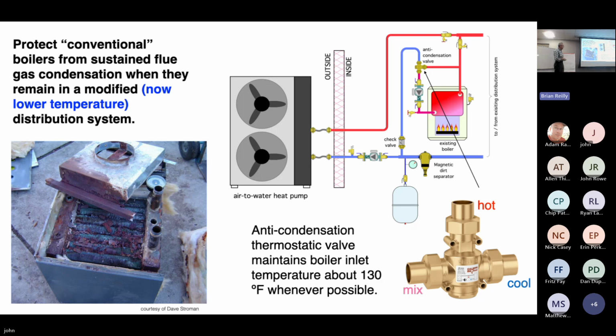Again, this is what happens when you run a conventional boiler at conditions that allow sustained flue gas condensation. That's an example of one of those thermostatic anti-condensation valves. Caleffi makes them, Danfoss makes them. They're readily available on the market. And there's no electricity. These are just thermostatic elements that are in here.